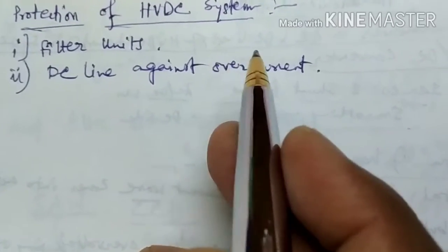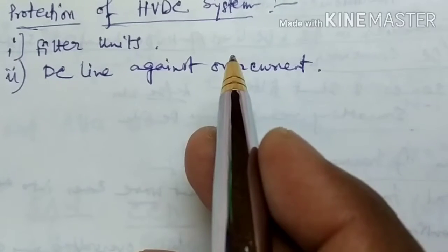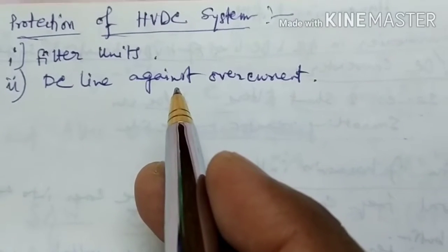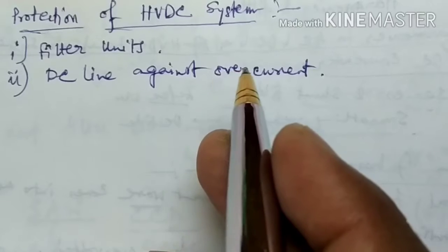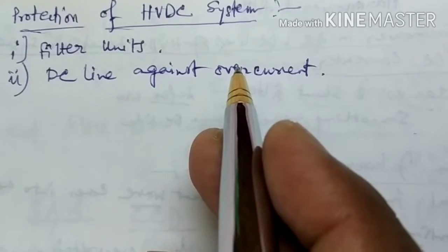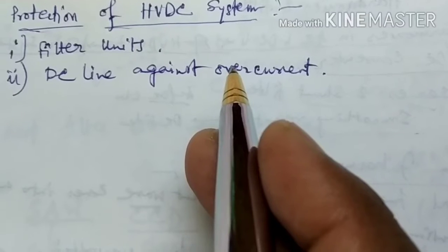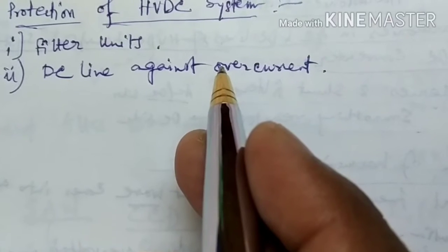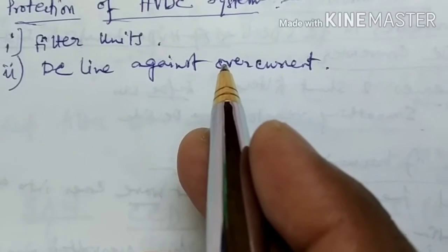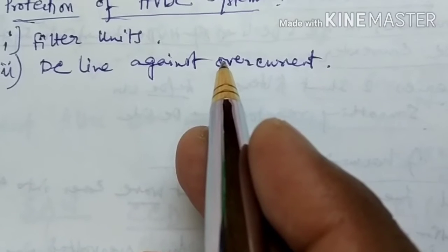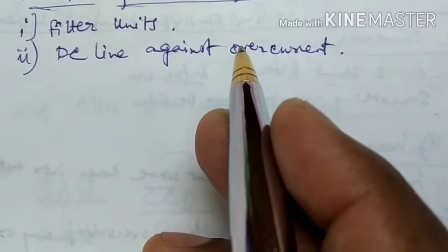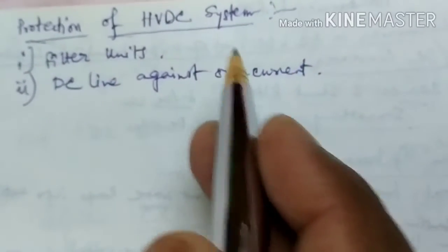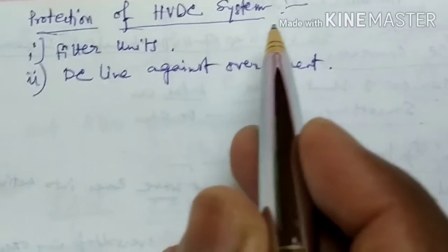The entire unit is connected through suitable circuit breakers, and the capacitor as well as inductor are provided with their own surge arrestor which protect them against over voltages when a fault occurs or is cleared, as well as against lightning and switching impulses. Usually, if a persistent short circuit or overcurrent occurs, the banks are switched off and put into service manually after fault clearing. This is the first point for protection of HVDC system.